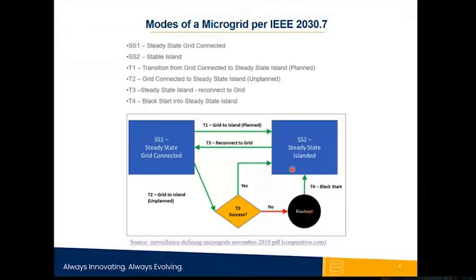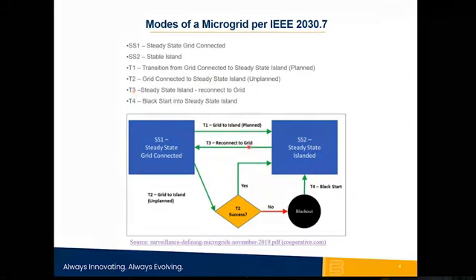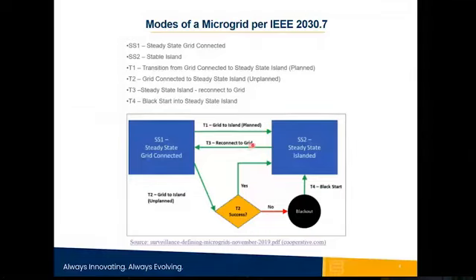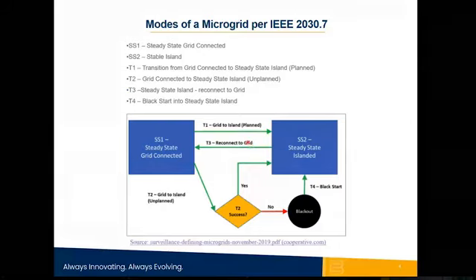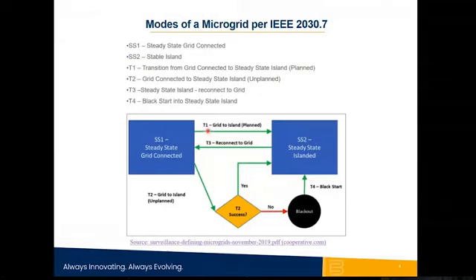And of course, there is the final transition. We skipped over T3 and went to T4, but T3 is steady state islanded to grid connected. So when conditions on the grid have been restored and the power is restored, the feeder is now stable, meaning that the voltage and the frequency are within acceptable limits. We transition back to the grid because it's the normal source of power. So these are the defined states and transitions as per IEEE 2030.7 in terms of the various modes in which a microgrid operates.